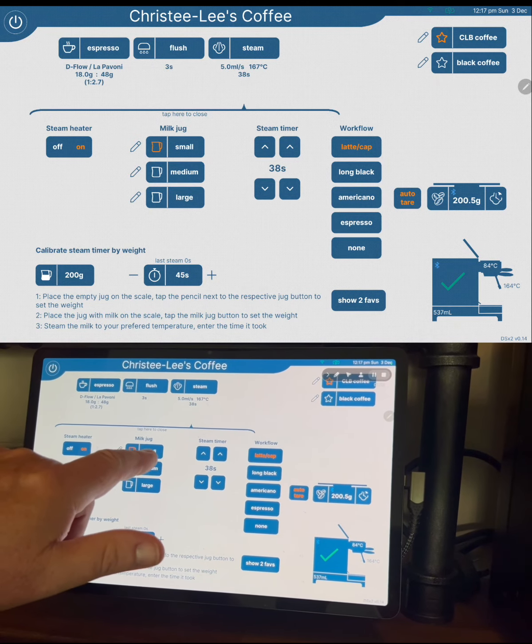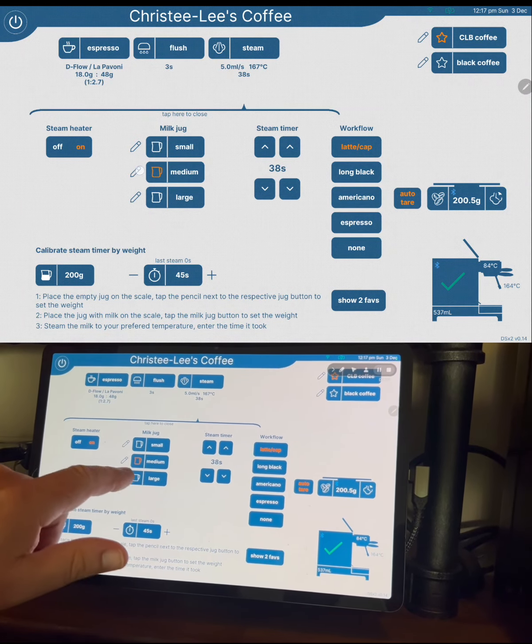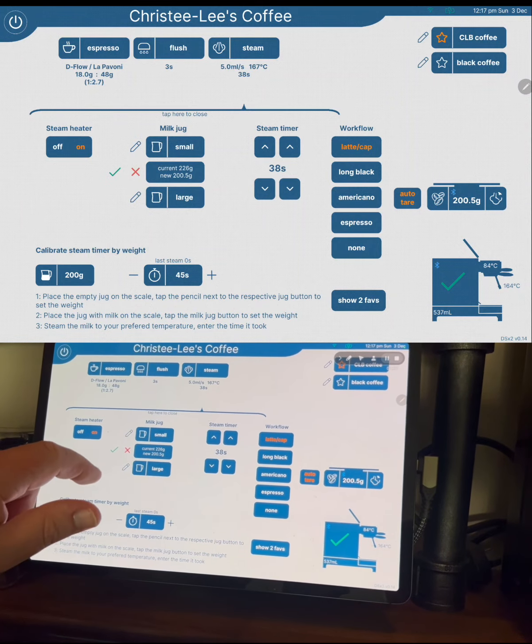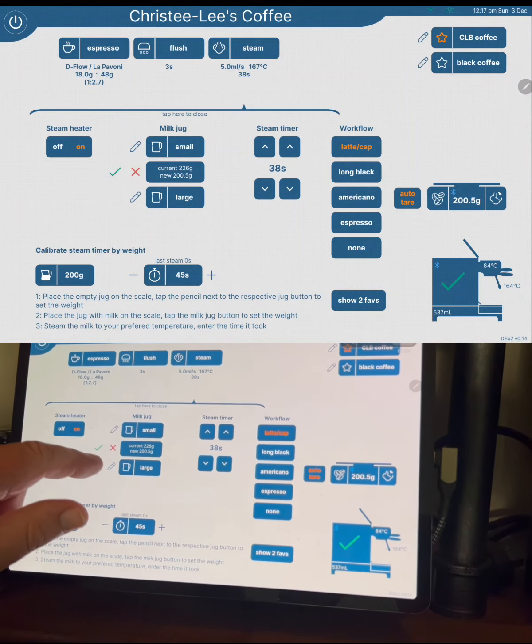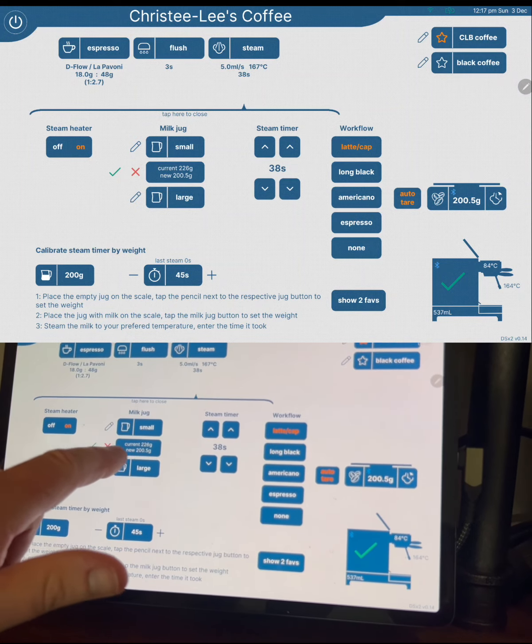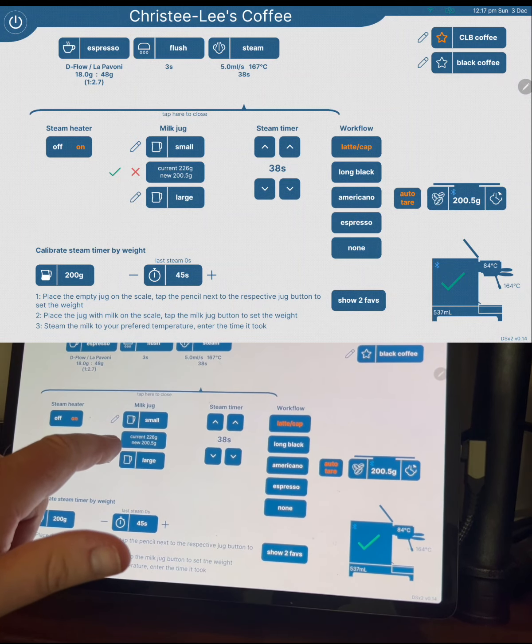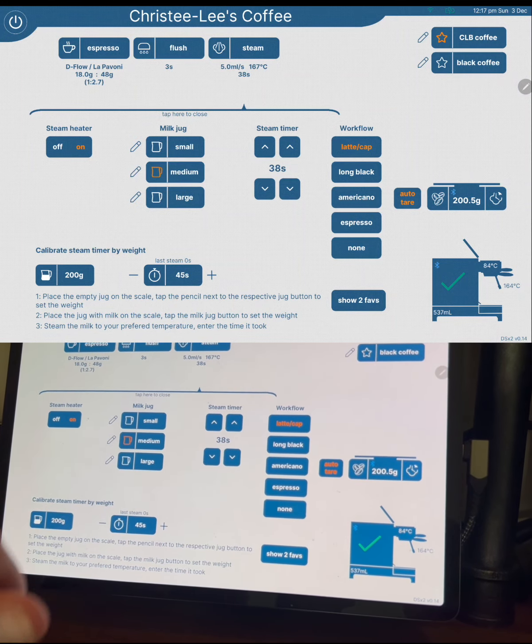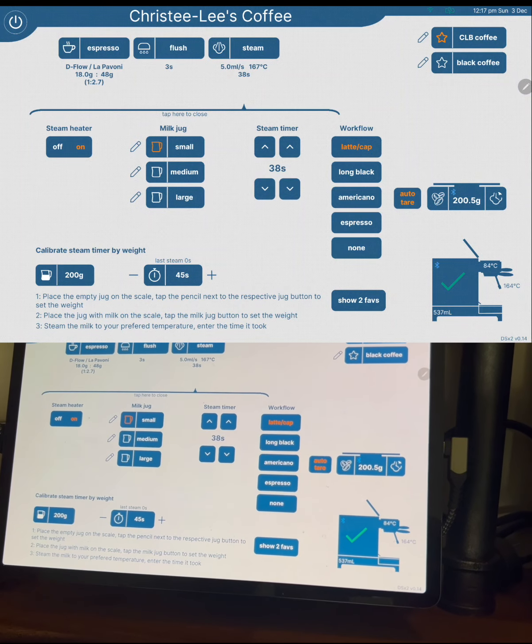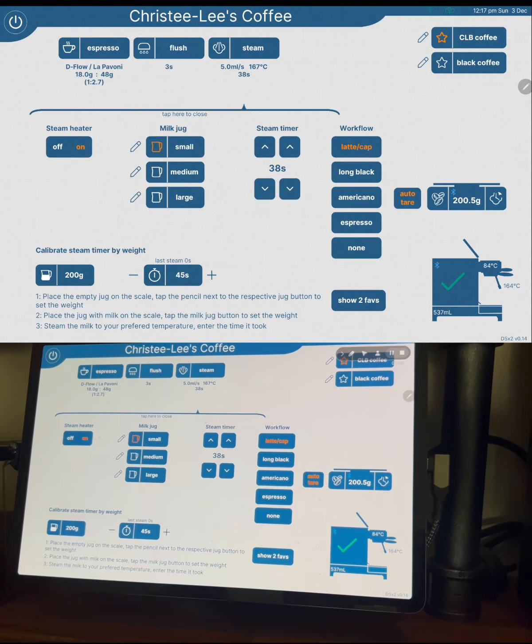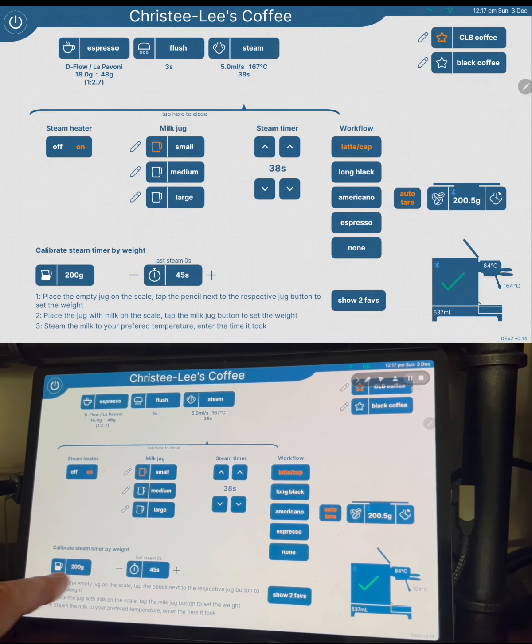Now we need to make sure that's selected, because if we're on a different button that's got a different weight, it's not going to work properly. I don't want to update the weight now, so I'm going to tap the X, and I'll close out without changing it. I'll select the jug we're using. Now we'll go through and set up this calibration.